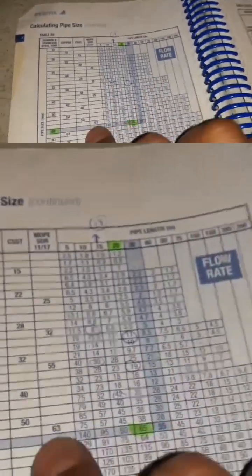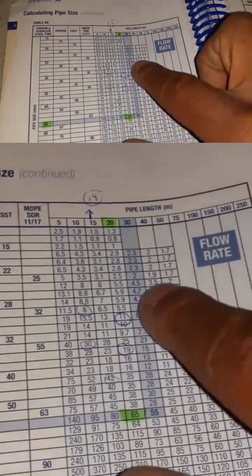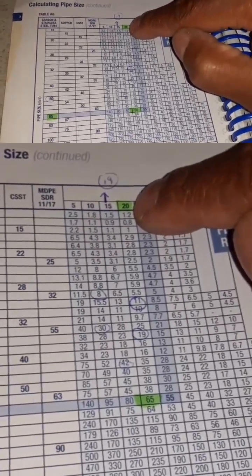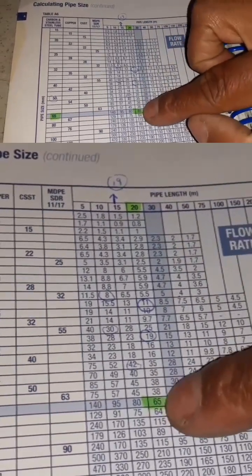We turn over the page and it shows you here: 65 millimeter will get us to 20 meters straight line of gas and give us this flow rate.